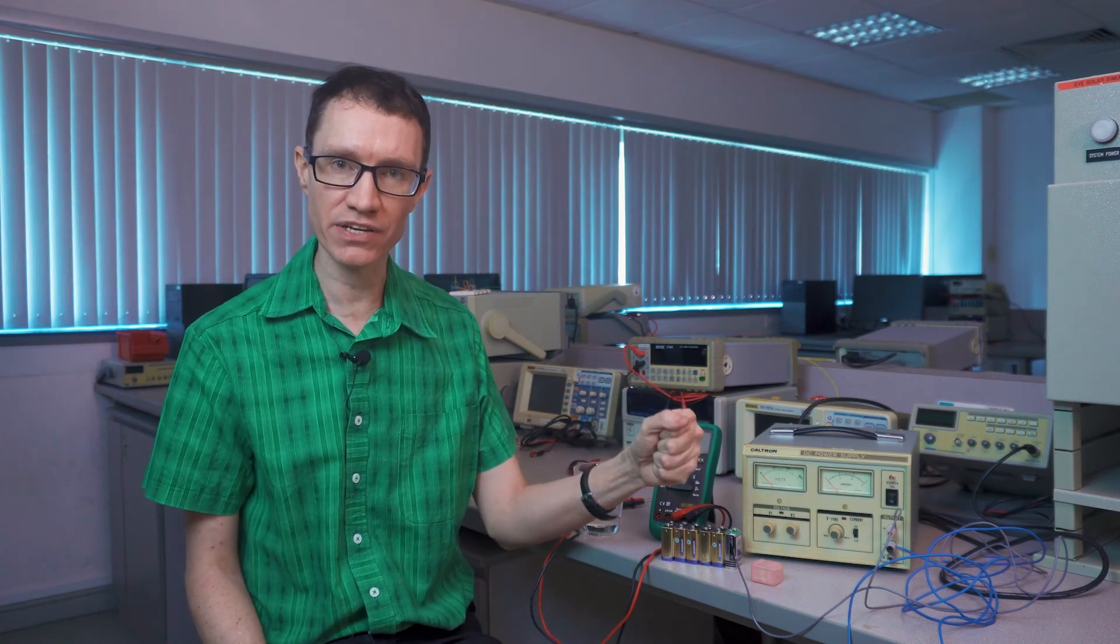I'd like to share with you a few tips when working around electricity. First of all, it's never a good idea to touch a conductor with the palm of your hand. The reason for that is if a conductor happens to be live and at a sufficiently high voltage, touching it or even tapping it with the palm of your hand can cause your hand to suddenly grip the conductor because your muscles would contract. If you grip a conductor and can't let go, then the situation can prove fatal. On the other hand, if you tap a conductor or touch it with the back of your hand, then contracting muscles will try to pull your hand away from the danger, which is a lot safer.